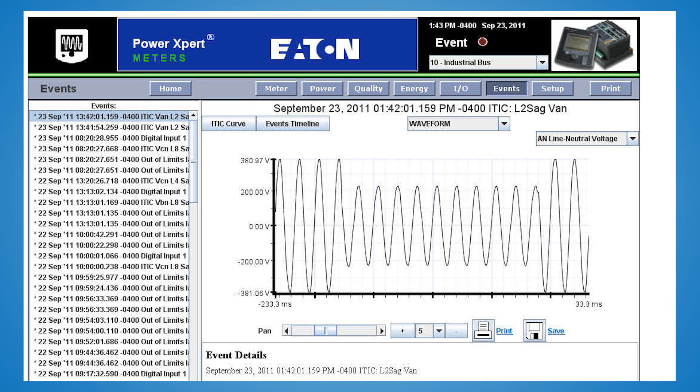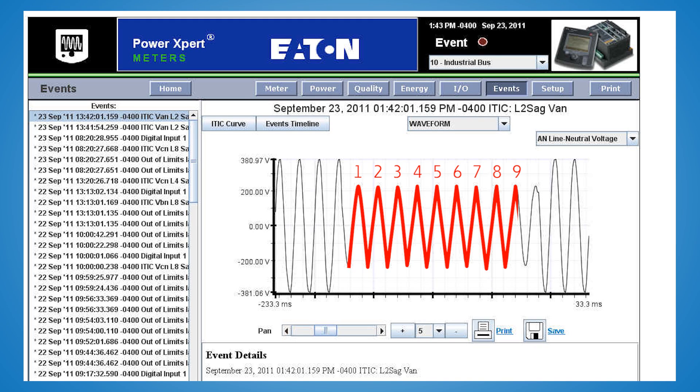For example, with this waveform, the retained voltage is 60% of normal, the duration of the event is 10 electrical cycles, and all three phases were affected. Voltage sags are considered the most costly power quality event because they're very common and they generally affect your whole facility.